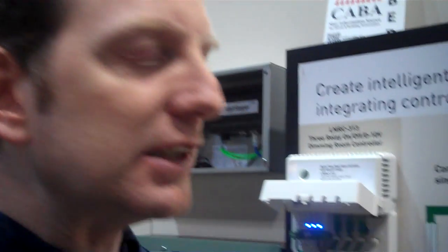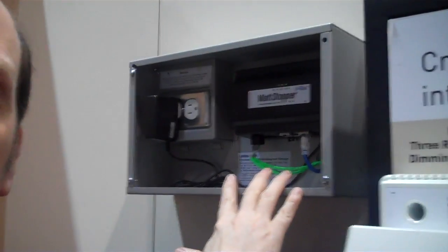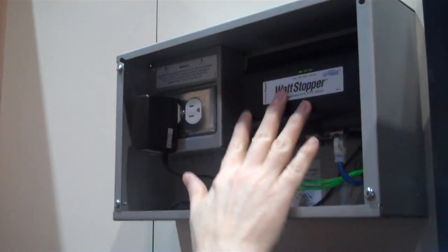The room will operate by itself with nothing else. We've already got an occupancy sensor, there's no front-end software required. Everything works and meets the code. But if you want to, we can add another little device inside this room, and now you've got a BACnet connection to that room. So now we can run an MSTP BACnet wire from room to room to room back to what we call a segment manager. Segment manager allows us now to offer the features that people are looking for in a whole building solution.